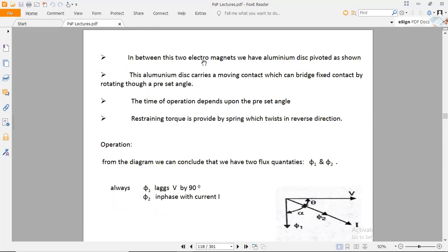In between these two electromagnets, we have an aluminium disc which is pivoted as shown. This aluminium disc carries a moving contact which can bridge the fixed contact by rotating through a preset angle. The time of operation depends upon the preset angle. Restraining torque is provided by a spring which twists in the reverse direction.